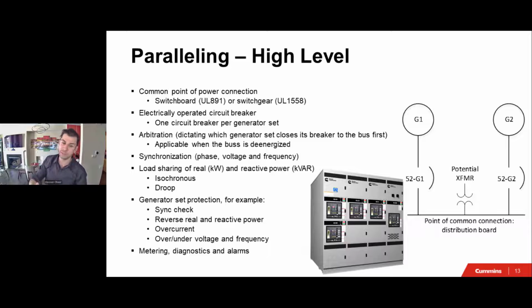The next thing we need to think about is load sharing. With load sharing, we have to share both the real and reactive power equally amongst the generators, and we're going to talk about isochronous versus droop. And then there needs to be some kind of protection. I have a slide to talk about generator set protection: things like sync check, reverse power, over voltage, under voltage, over frequency, under frequency, reverse reactive power as well. And we need to have some kind of metering, diagnostics, and alarms.